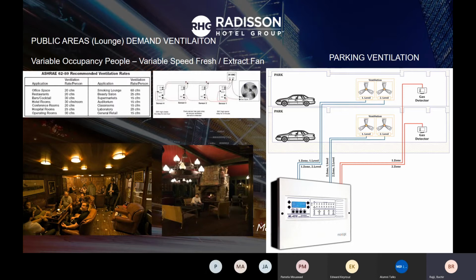So if the design of this area would accommodate 20 seats or 20 persons, we multiply this number of people by the CFM. So we have to ensure the fresh air and extract rate copes with this standard. And then we run the fan always on full capacity as designed, 60 CFM times 20, and extract the same. In the sustainability approach with demand ventilation, instead of running on full capacity all the time as per the code, we install what we call an air quality sensor on the system, mainly a CO or CO2 sensor. So it will measure depending on the number of occupants, and the people who are smoking, maybe you have 20, but only 2 smoking.